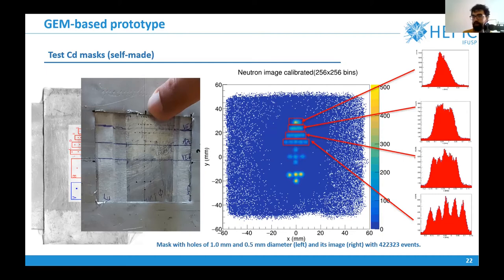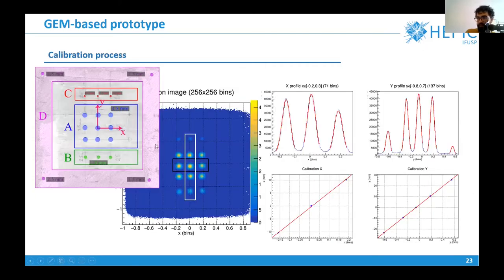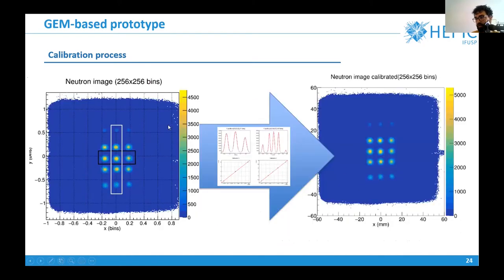Here we can have an idea about the resolution, spatial resolution of our detector. This mask we used for the calibration, for position calibration of our detector. We can plot here in the white the white region, we can plot the Y profile and the X profile of the black region here. We know the positions because of the calibration of the mask. Knowing the real positions of these holes and their position in bin coordinates, we can get the calibration equations and we are able then to calibrate the position of this image.